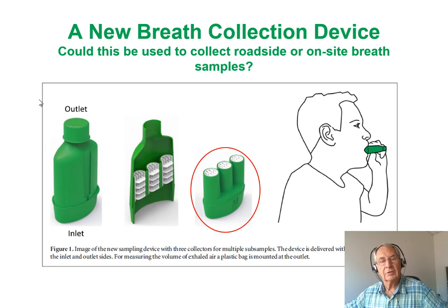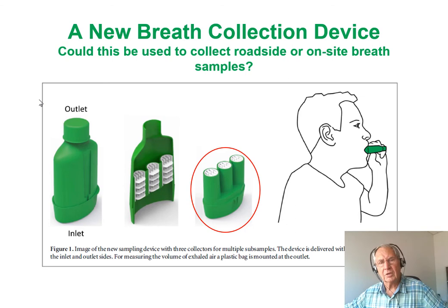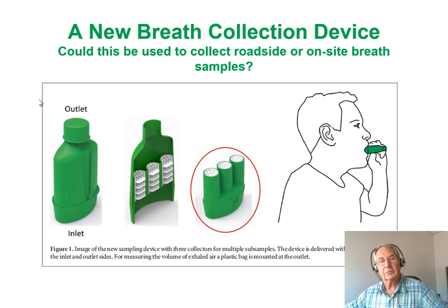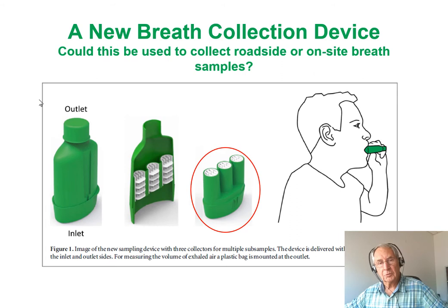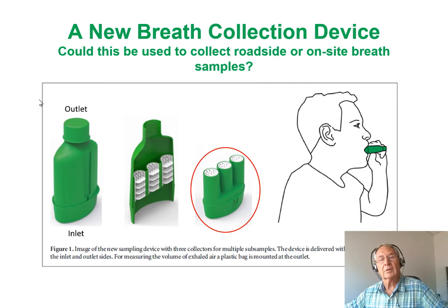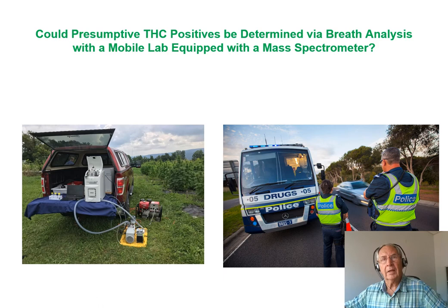For forensic drug testing, having three collectors is very handy: a screening test can be done on the first, and if that's a presumptive positive, the sample can be analyzed again by a central laboratory, and even a third reference laboratory if necessary. When you remove the upper portion of the device, you see the collectors, which can be pushed out easily into a vial and extracted. The condensate from the breath inside the collector is pushed into a vial, extracted with a solvent — in this work, absolute ethanol — and that extract is analyzed by LC-MS.